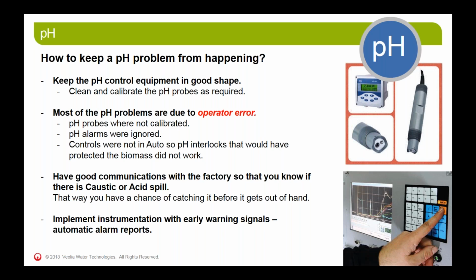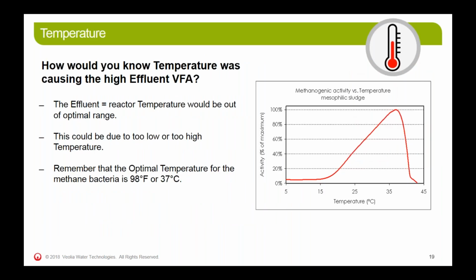And then the controls, if they're not in auto, the interlocks that might happen at high or low instances, which would shut the system down, don't work unless everything's in auto. And so that's another thing you've got to make sure that you do. Keep everything in auto. Again, have good communications with the factory so that you know if there's an acid or caustic spill, and then you have a chance to catch it before things get bad. And again, your controls, keep them going.